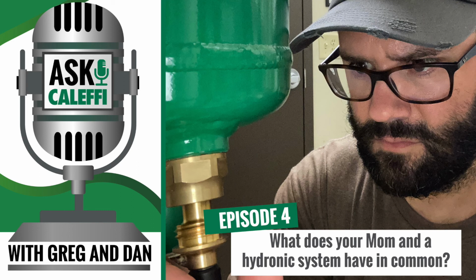So I've got another question for you, Greg. Most of our dirt separators have either a plug in the top or a stem with a cap off the top. What's the purpose of that? That's a great question. I've seen plenty of contractors actually add an additional air vent on them. Because they have the coalescing mesh in there, yes, it's removing dirt, but it will also catch any air bubbles coming in. So it's like a secondary air removal device. Yeah, the smaller brass ones have a 1/2-inch female NPT connection where you can put one of our MiniCal or Val-Cal 1/2-inch air vents on top, and you get a little bit of additional air separation.